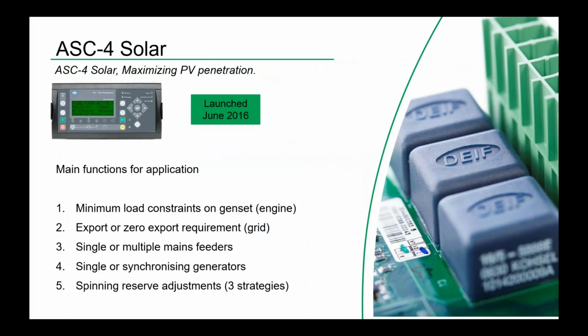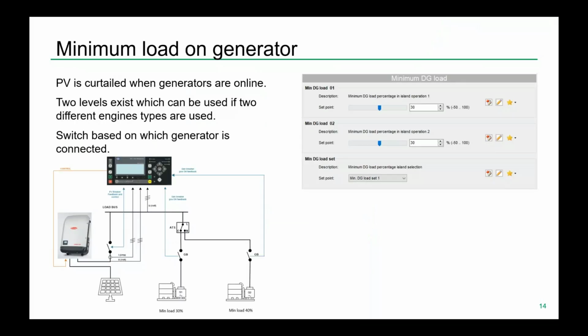Let's see a little about how we do this. If we look at the main points, we can say minimum load of the generator. Which settings do we have? How do we do it? We have two settings: minimum load DG level 1 and level 2. And if, like the drawing shows, you have two generators, generator 1 with a minimum load of say 30% and generator 2 with a minimum load of 40%, if they are non-synchronized, you can swap between set 1 and set 2, and then they will run at their own optimal minimum load. To note, if you have a synchronized system, it's a compromise, then you have to set one shared minimum load. But with the settings, you can toggle this, or you can do it automatically.